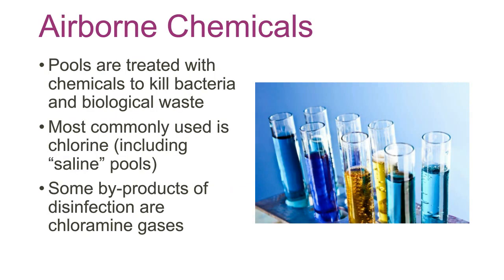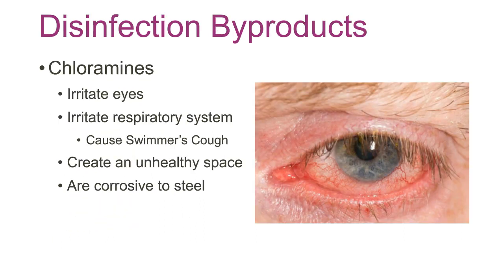I mentioned the chemicals. So the pools are treated with chemicals to kill bacteria and biological waste, chlorine being the most common one because it's the most cost-effective to deliver and the most effective. Saline pools, if you've heard of those, are really just another way to deliver chlorine. So chlorine is definitely most commonly used, and you have byproducts of that disinfection process, chloramine gases. Chloramines are an irritant to the eyes. They're an irritant to respiratory systems. If you've heard of lifeguard lung or a swimmer's cough, usually that's what is causing that, what people are referring to. They can create a very unhealthy space. And as I mentioned, the corrosion from humidity, well, they're also very corrosive to steel.